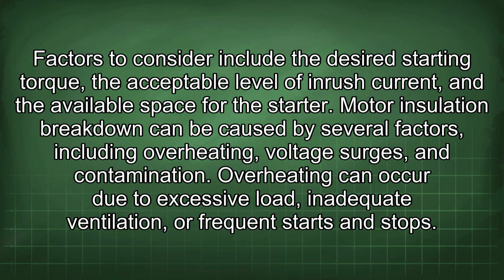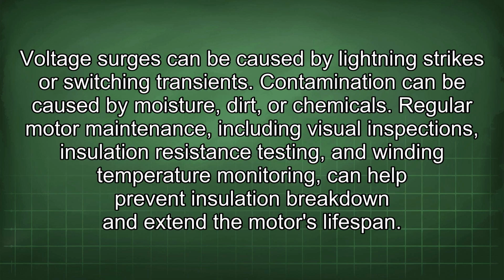Motor insulation breakdown can be caused by several factors, including overheating, voltage surges, and contamination. Overheating can occur due to excessive load, inadequate ventilation, or frequent starts and stops. Voltage surges can be caused by lightning strikes or switching transients. Contamination can be caused by moisture, dirt, or chemicals. Regular motor maintenance, including visual inspections, insulation resistance testing, and winding temperature monitoring, can help prevent insulation breakdown and extend the motor's lifespan.